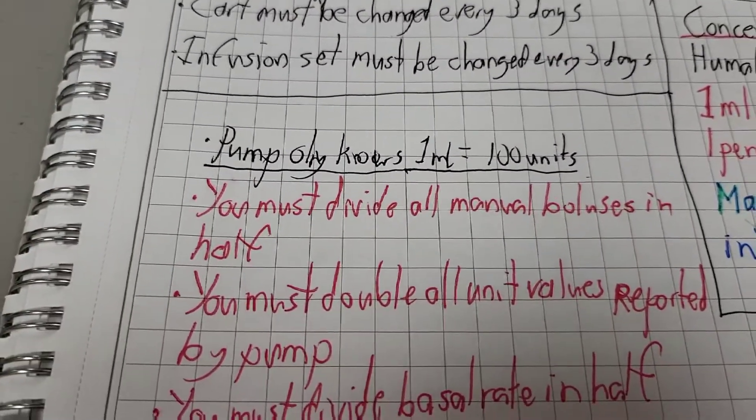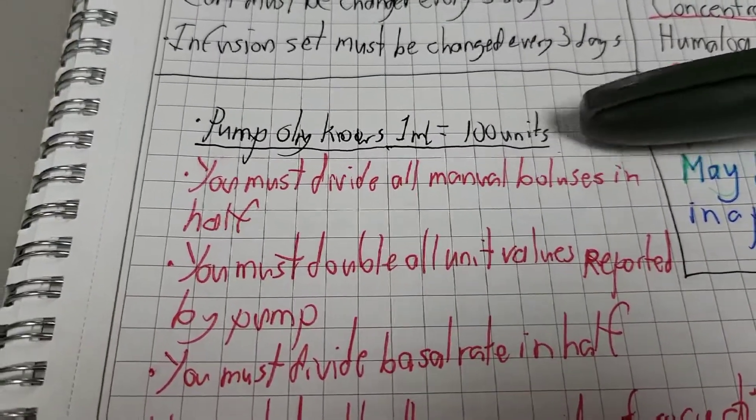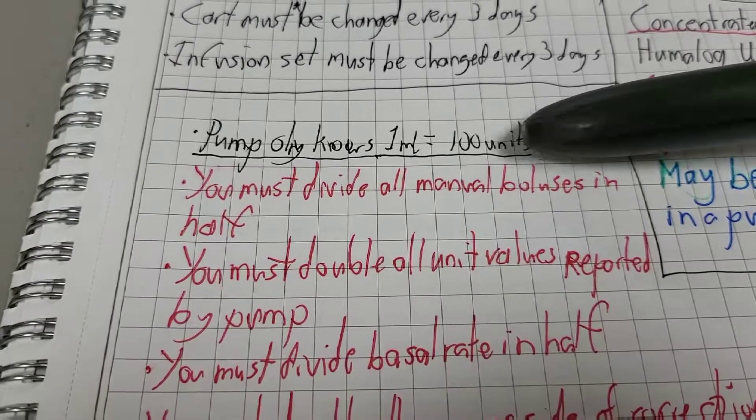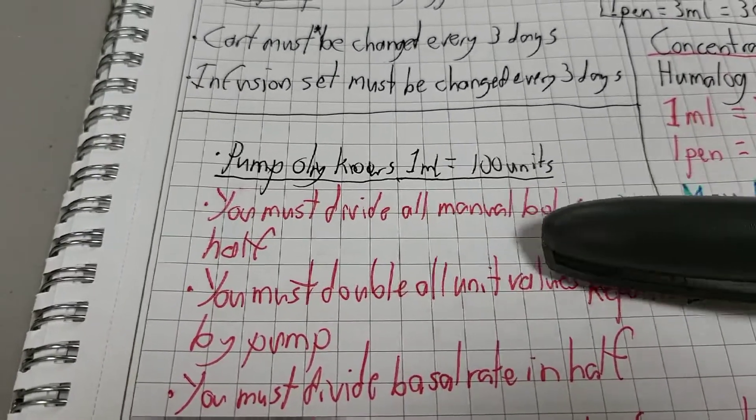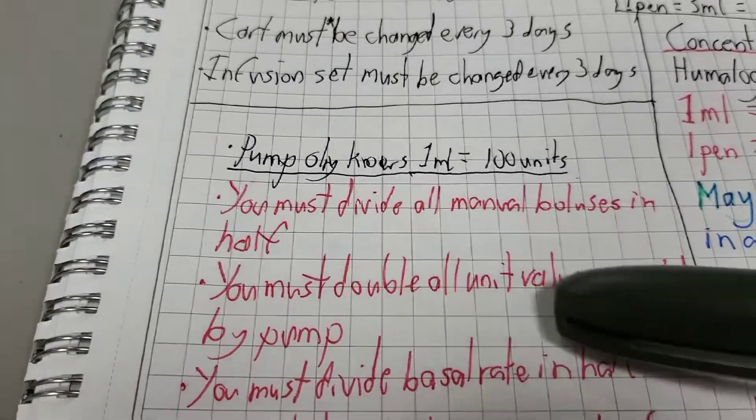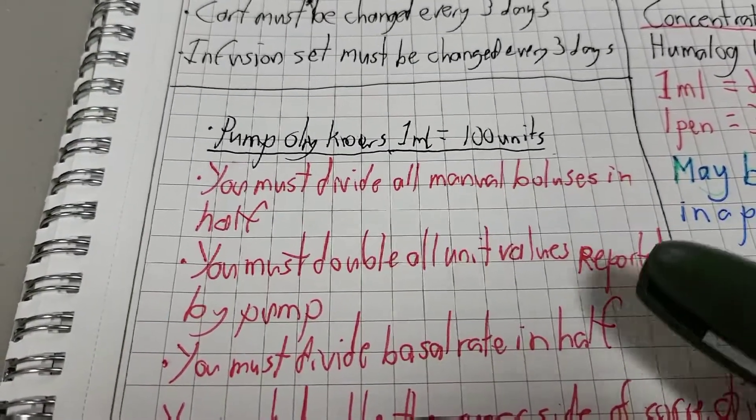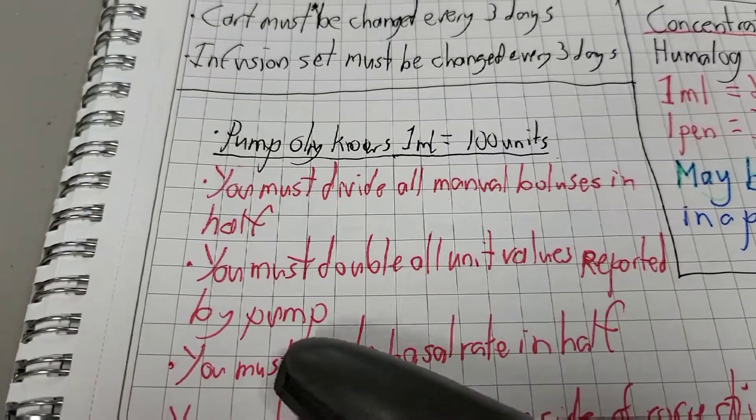So the caveats to using U200 in a pump. You have to remember that pumps only know about U100. Any manual boluses you perform, you have to divide in half. On the flip side, when you are viewing the data in the pump, all the unit values reported, you have to double.